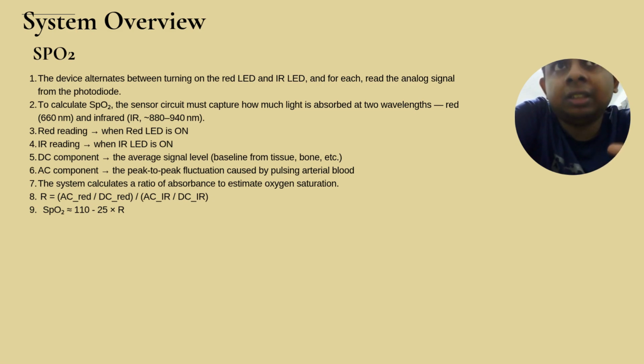The DC component is the constant, the average signal baseline from the tissue, bones, etc. The AC component is the peak-to-peak fluctuation caused by pulsing arterial blood. The system then calculates the ratio between the absorptions to estimate oxygen saturation. So the ratio we calculate is AC red over DC red, divided by AC IR over DC IR, and then we use this formula: SpO2 equals 110 minus 25 times R.